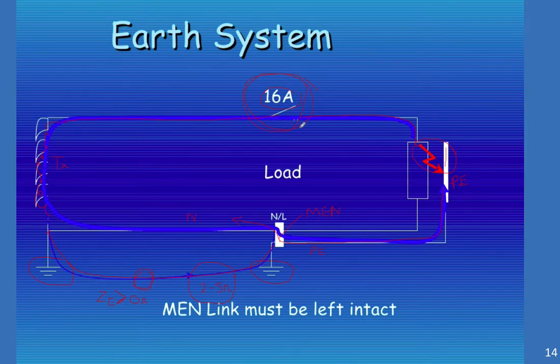The difficulty is, if we rely on this body of earth to do the tripping of the circuit breaker, because the resistance in here could be as high as two, maybe to five ohms, we will not get sufficient trip current to flow to make our protective device do its job. And that's the whole problem. So the MEN link must be left intact.